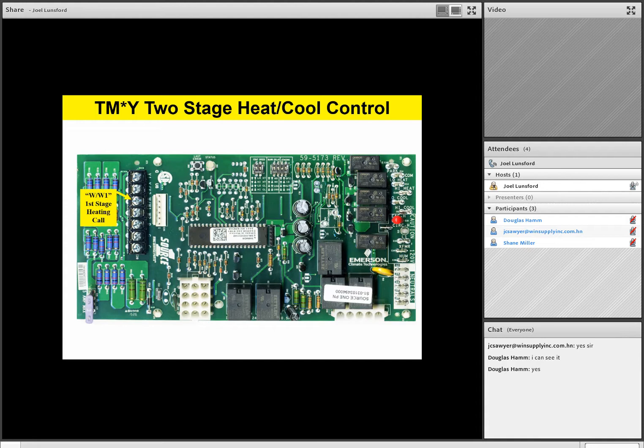If you have a two-stage thermostat, it's your first stage heating call, W1. But if you only have a single-stage thermostat, you land it on this W/W1 terminal. And if you have a two-stage heating thermostat, your W2 will then go to your W2 terminal for your second stage heating call. Any questions or comments on that before we continue? Okay. So remember, if you have a single stage thermostat, be sure and land your W terminal on the W/W1.